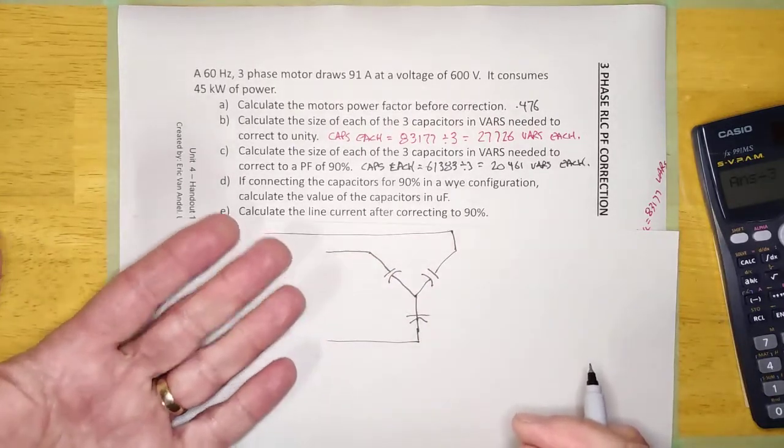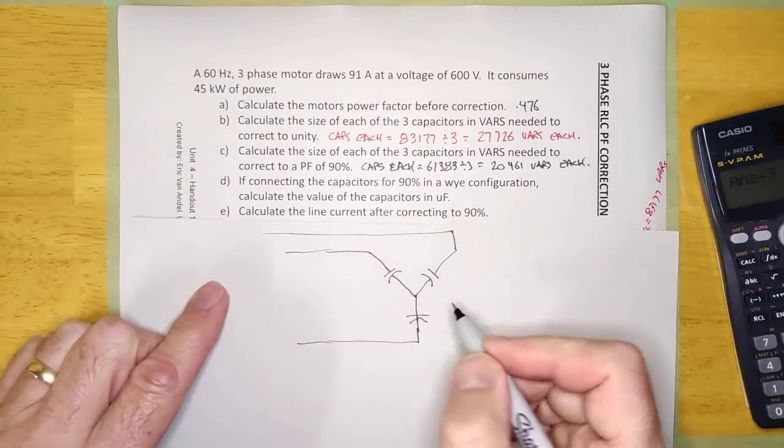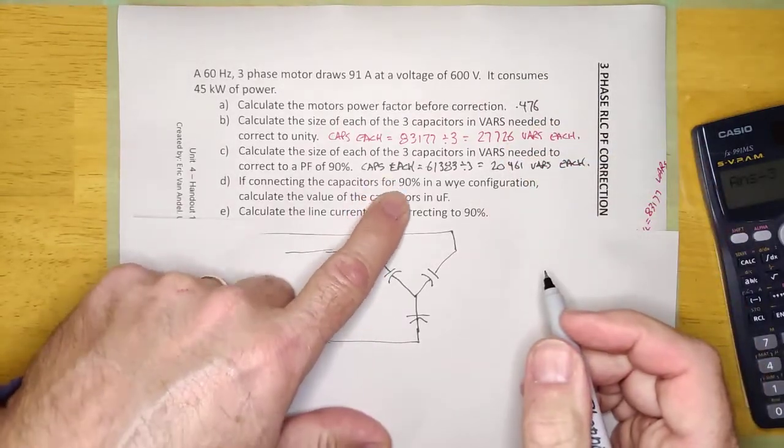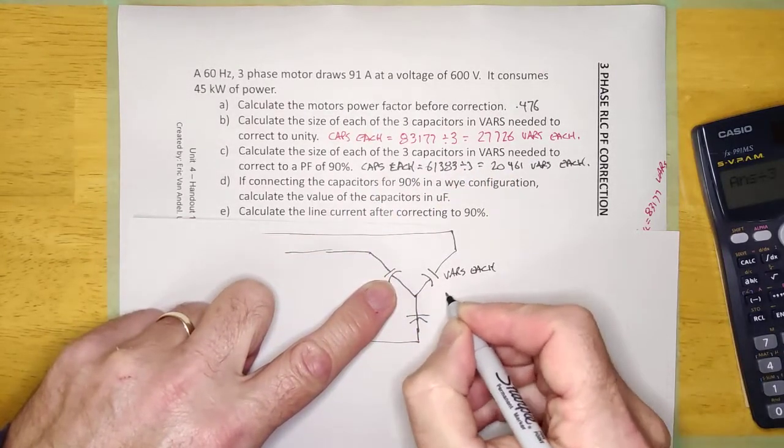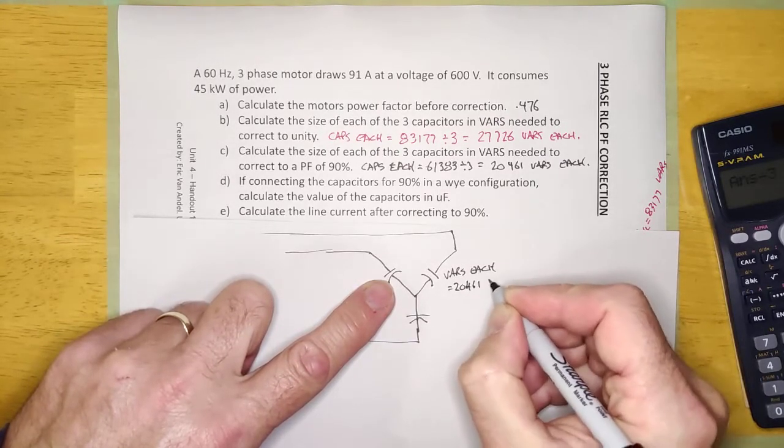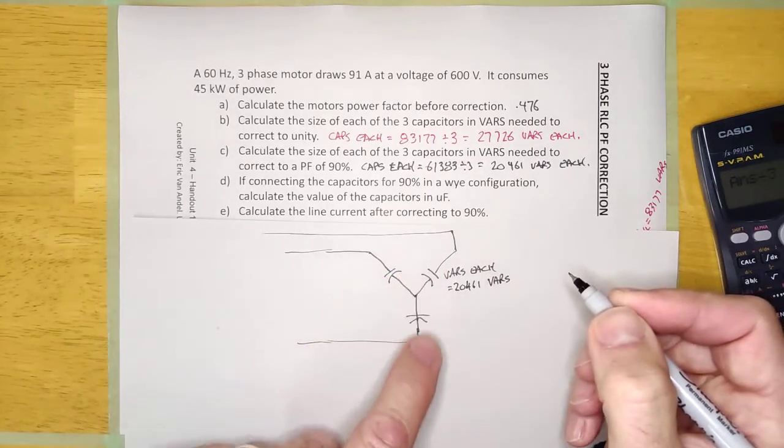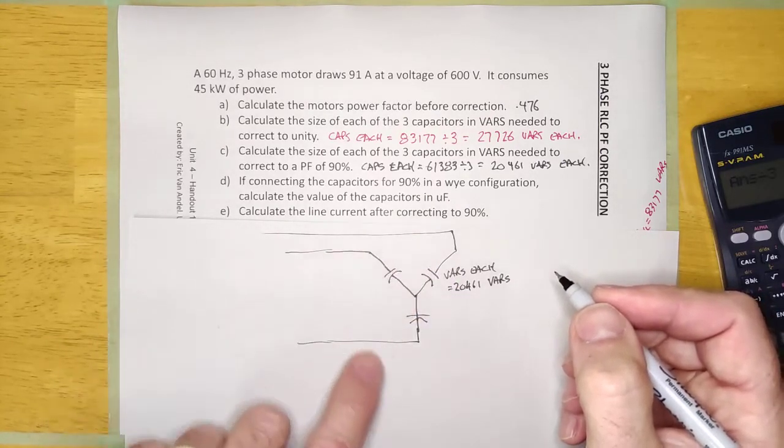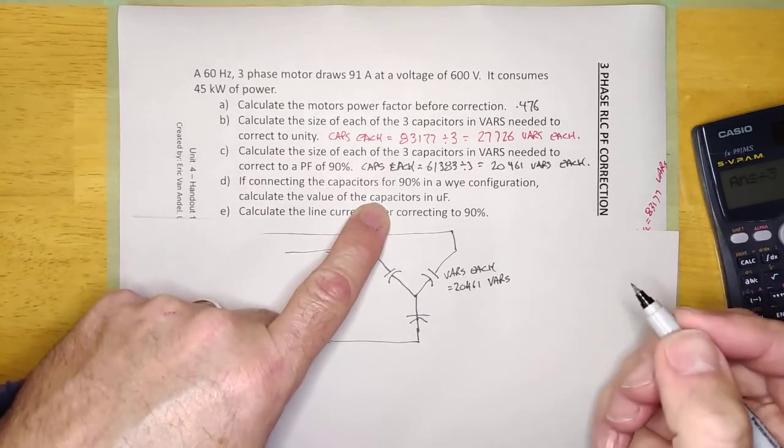It doesn't say if it's Y or delta, and it doesn't really matter. It's connected out here in parallel with it. Now, we just calculated that this thing here is 20,461 VARs. And so, that one's 20.4K VARs, all three of them. And it's asking, calculate the value of the capacitors in microfarads.